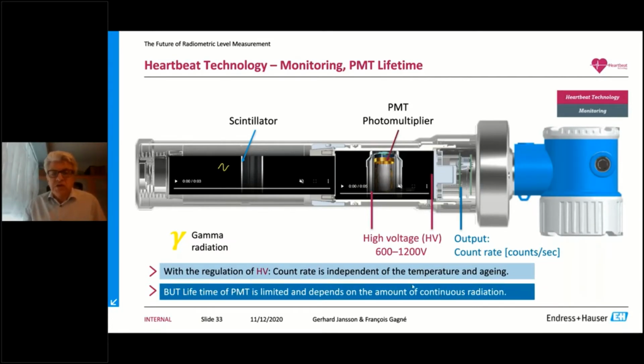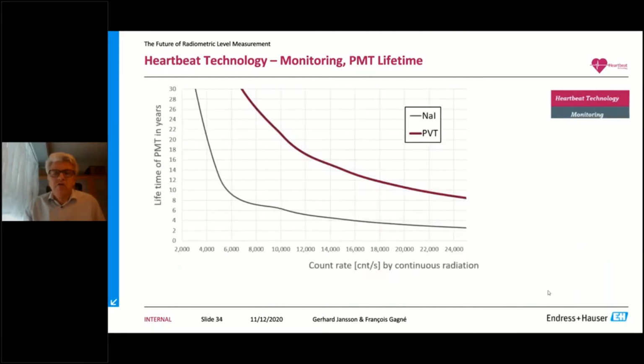But this is of course a way that we can see how much life expectancy we still have on this device. Temperature is one factor. It's also the number of years it has been in operation, but it's also a matter of what radiation level we expose the detector to. So at the bottom here, you see the number of counts per second, and here it's the number of years of life expectancy.